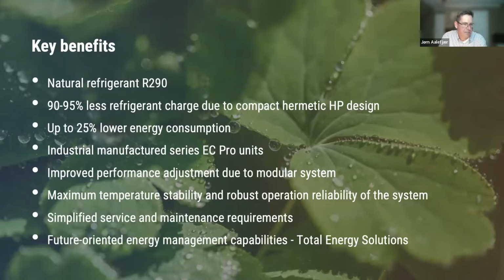So, key benefits of R290. I know that this is something that needs to be totally clarified in this country. There's an indoor charging limit and an outdoor charging limit, and I would say it is not 100% clear how it's going to be handled. Since the heat pump is a very small circuit, we use 90 to 95% less refrigerant than we would in a direct expansion system. We now see here up to 25% lower energy consumption. I was a bit bolder in my previous slides because we see that that's quite conservative.